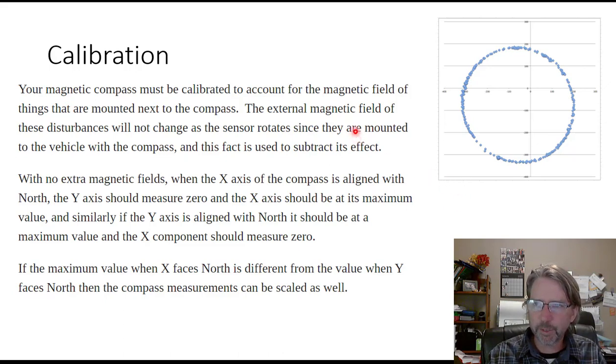And what the effect of the extra magnetic field is that if you rotate around and plot x versus y, we get this nice circle, and the angle, the heading, is based on the x versus y. But you can see the center of the circle is not at the origin, and that's what we have to fix. We have to add a constant to the x and y components to move this center back to the origin. Otherwise, when we do the arctangent, it's based on here, and so we'll use this angle from the origin to the points rather than the center of the circle to the points.